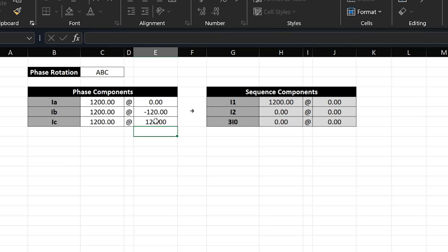Notice that I've entered a set of three phase currents balanced for an ABC system — these currents have an ABC rotation. You can see that because the B phase current has an angle of minus 120 degrees and the C phase current has an angle of positive 120 degrees. Also notice that the phase rotation for the system as I've defined it is ABC. That's the reason why we get purely positive sequence current: not only are the currents balanced, but they're in the same rotation as our system, which I've defined as ABC.